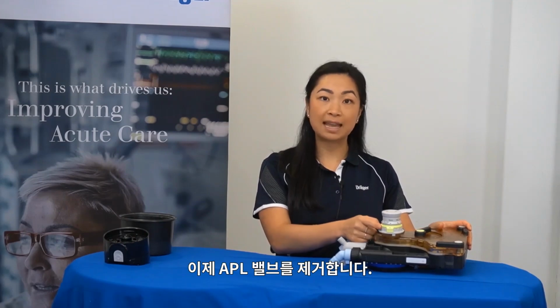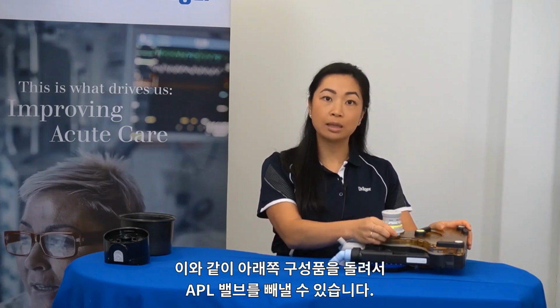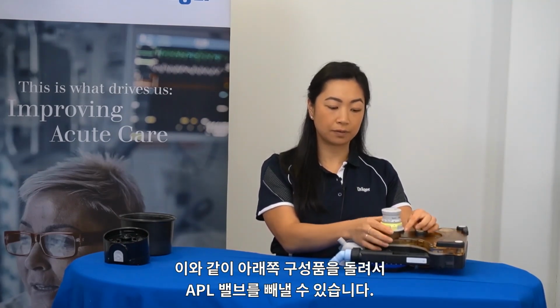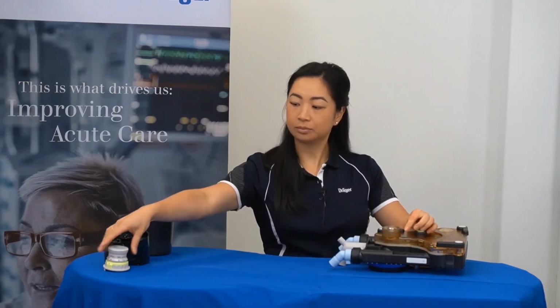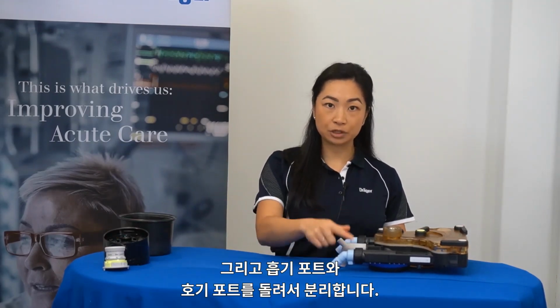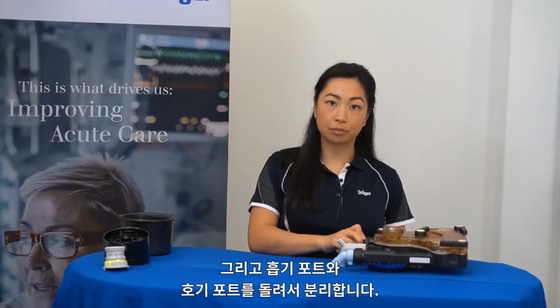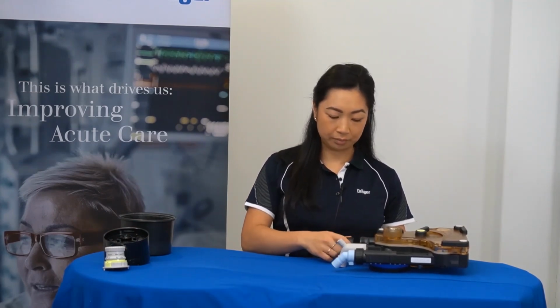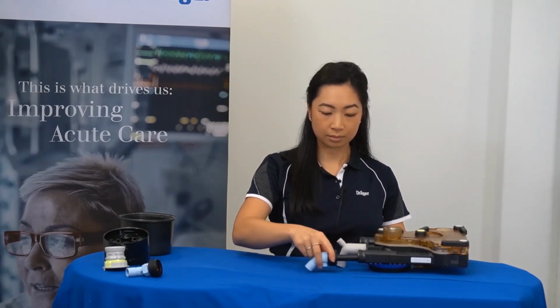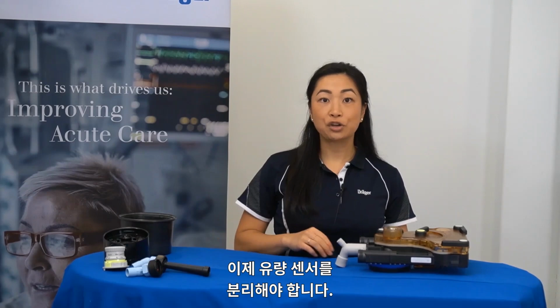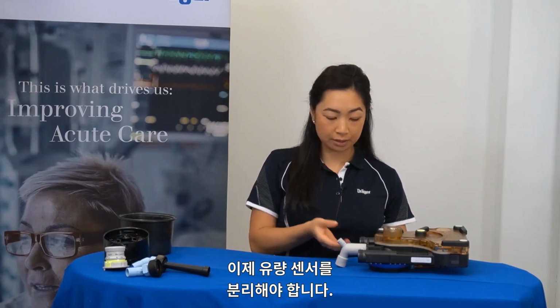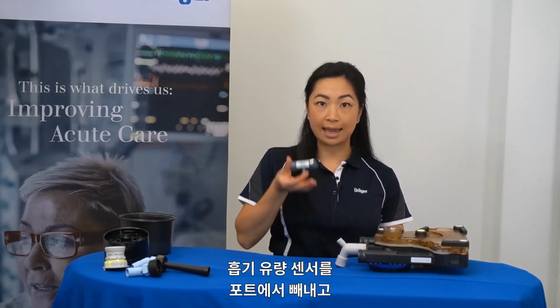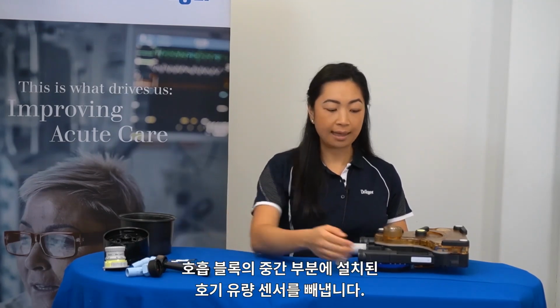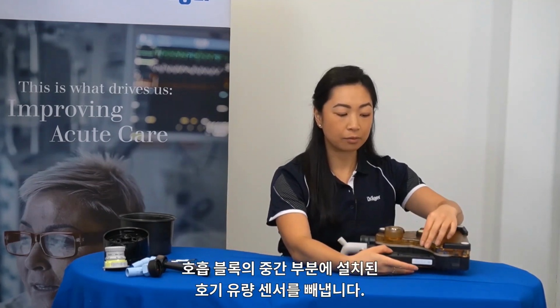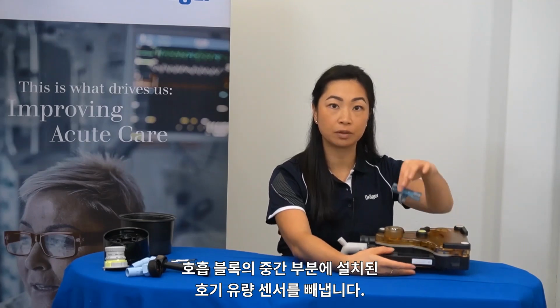You can then remove the APL valve by unscrewing the bottom component of the valve. Following that, the inspiratory and expiratory ports can be unscrewed from the block. Your flow sensors can now be removed. The inspiratory one by sliding out of the port, and the expiratory flow sensor by being removed from the middle of the breathing block.